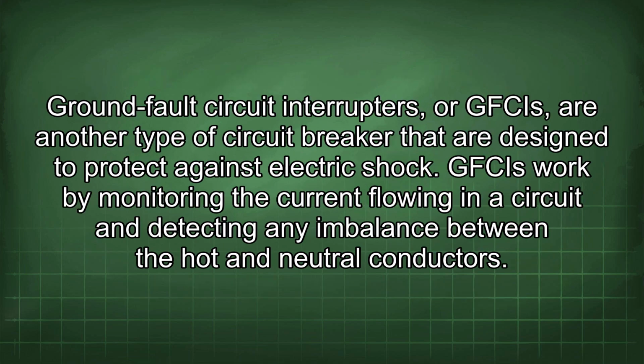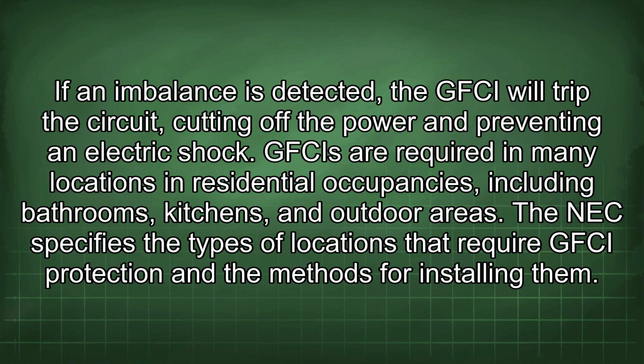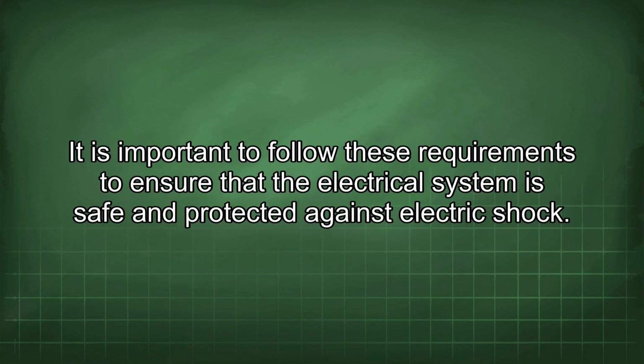Ground fault circuit interrupters, or GFCIs, are another type of circuit breaker that are designed to protect against electric shock. GFCIs work by monitoring the current flowing in a circuit and detecting any imbalance between the hot and neutral conductors. If an imbalance is detected, the GFCI will trip the circuit, cutting off the power and preventing an electric shock. GFCIs are required in many locations in residential occupancies, including bathrooms, kitchens, and outdoor areas. The NEC specifies the types of locations that require GFCI protection and the methods for installing them. It is important to follow these requirements to ensure that the electrical system is safe and protected against electric shock.